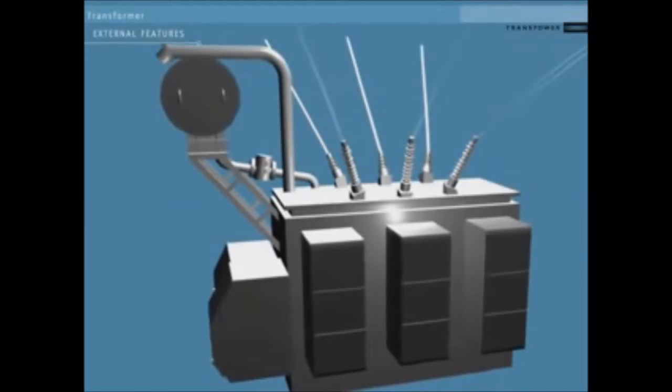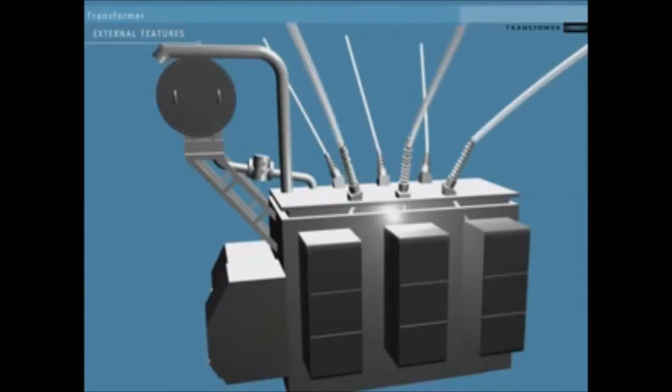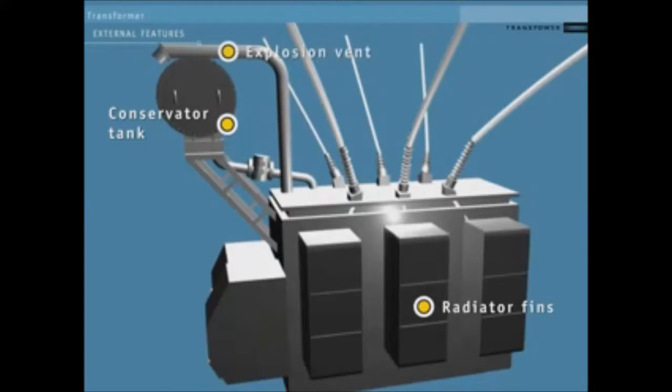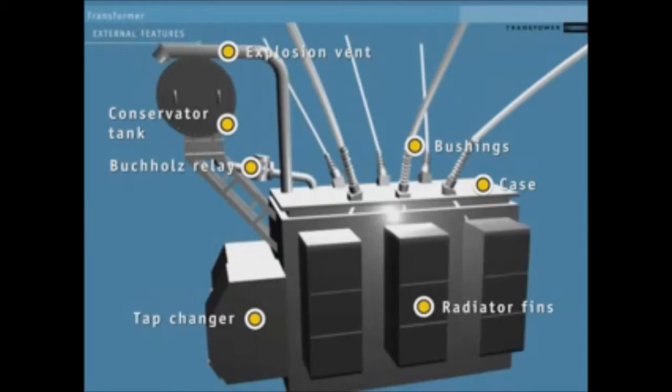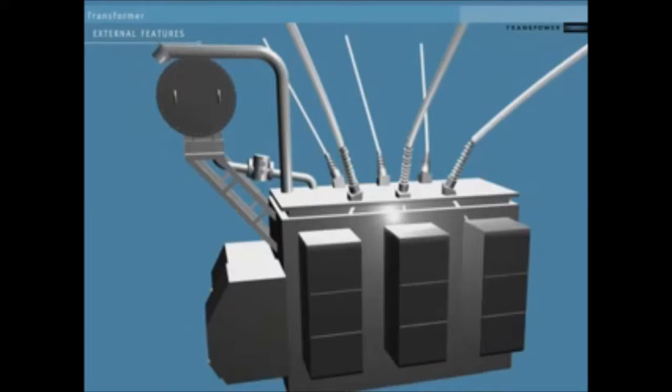On the outside of the transformer are a number of external components. Some help it to remain at a good working temperature. Some help make it safer in the event of an accident, and some are used for monitoring. The radiator fins help cool the oil in the case. The conservator tank allows for the oil to expand and contract as it heats and cools. The explosion vent protects the transformer in the event of a major fault. The bushings insulate the conductors where they enter the case. The tap changer sets the exact amount of voltage change. The Buchholz relay lets us detect the presence of gas caused by the deterioration of the oil and/or a rapid increase of oil pressure.